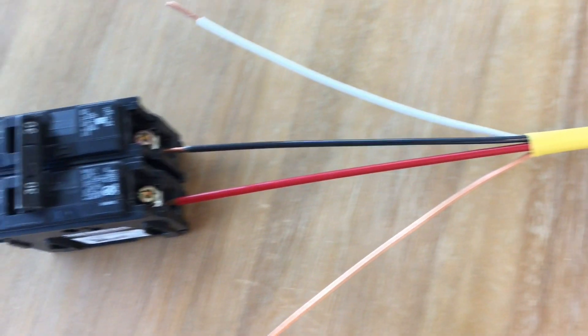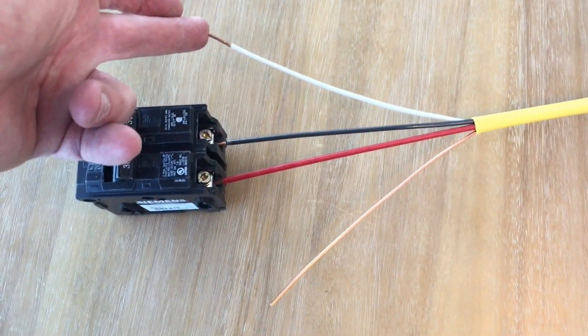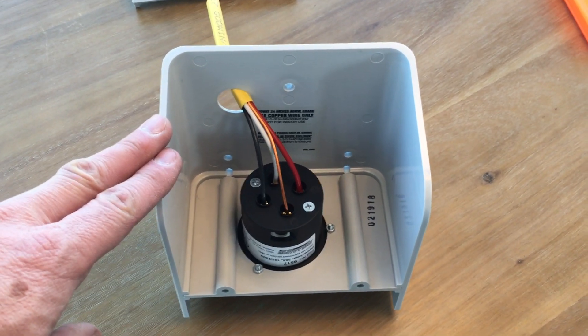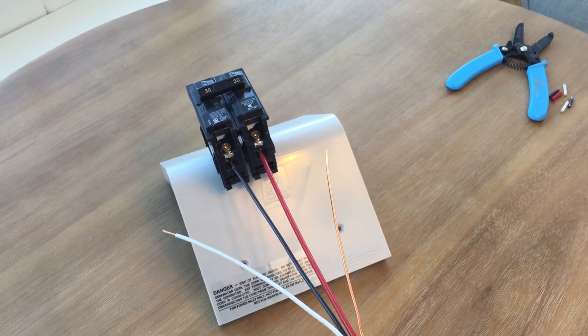At the other end of our cable, the black and red wires go into the circuit breaker and get tightened down with this set screw. This goes to the neutral bar, and this goes to the ground bar in the breaker box. In an actual installation, this box gets mounted to the wall, and this wire goes through the wall — maybe 50 feet or so — until you get to the electrical panel.